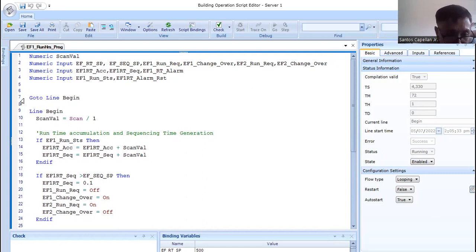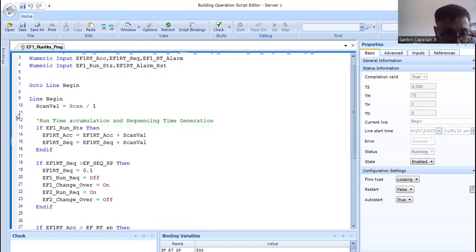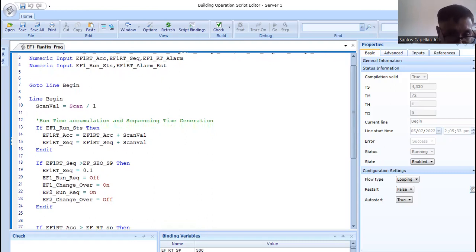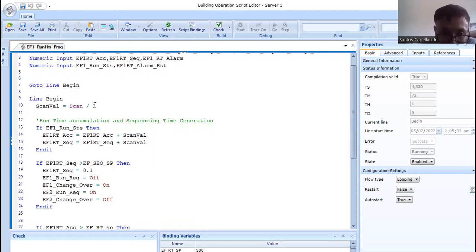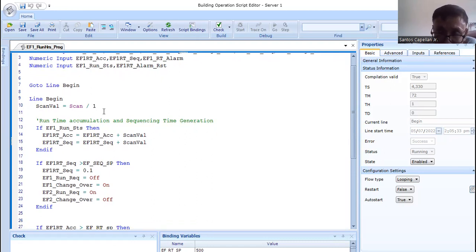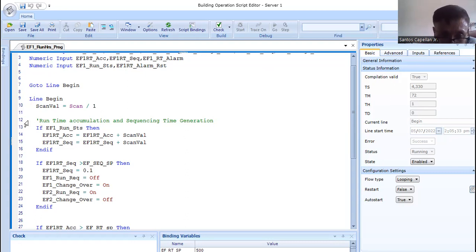After line six, the next instruction is 'Go to line Begin' — this is a jump instruction, so it will look for line Begin and start executing from there. Execution is sequential unless there is a jump instruction. Scan val is my variable and I'm using the built-in scan variable, dividing it by one. If I want to display hours, I divide by 3600; if I want minutes, I divide by 60; dividing by 3600 gives one hour.